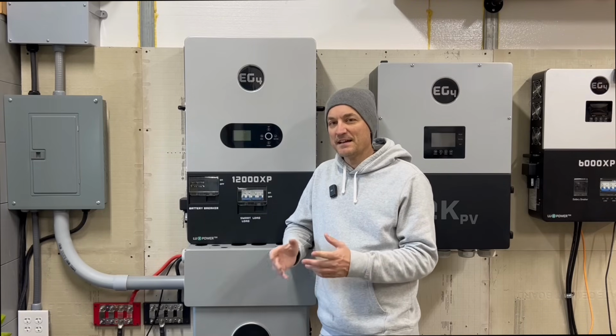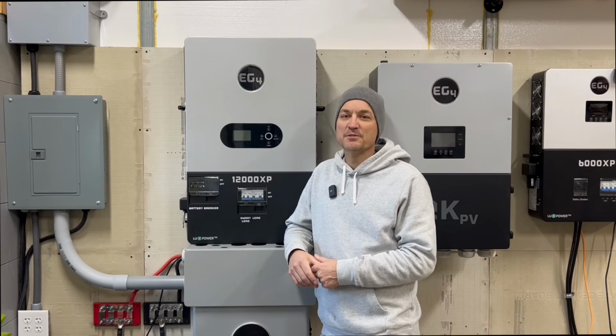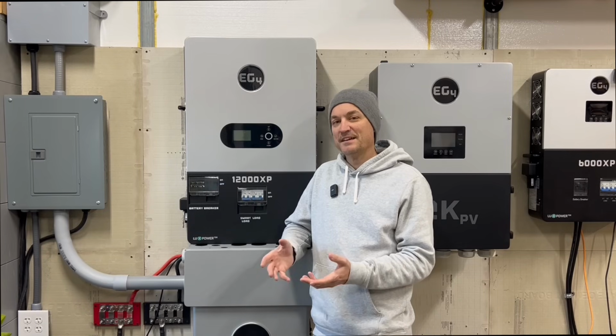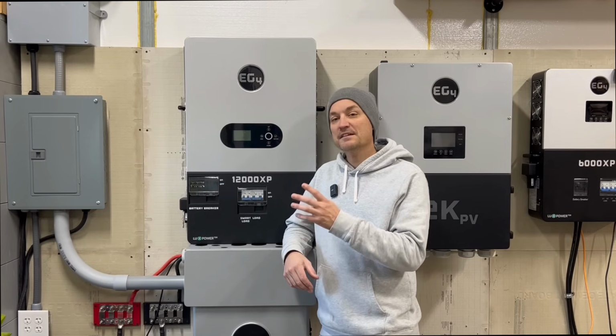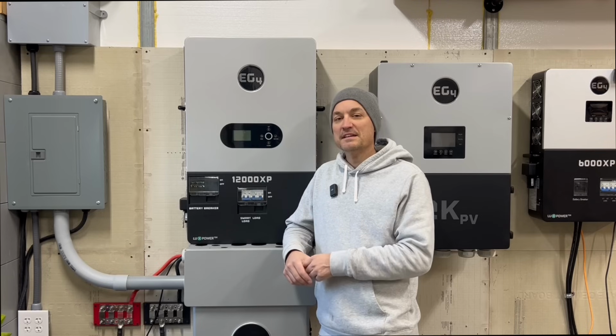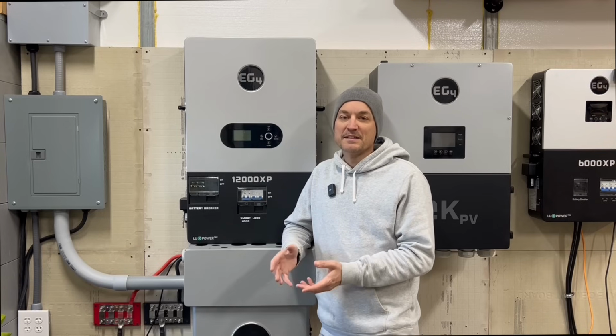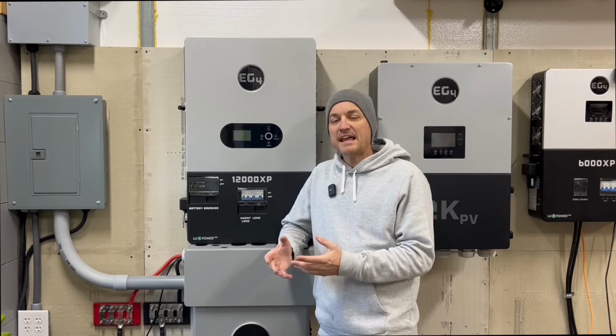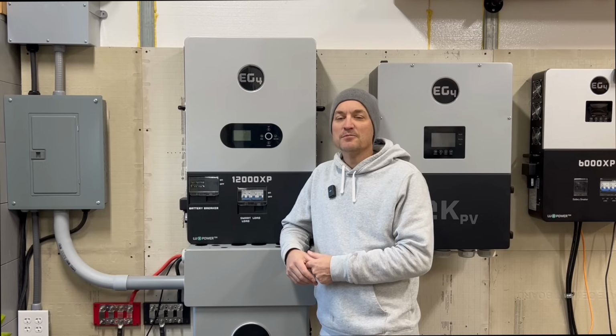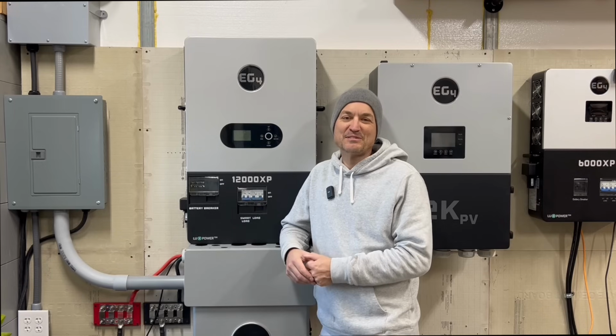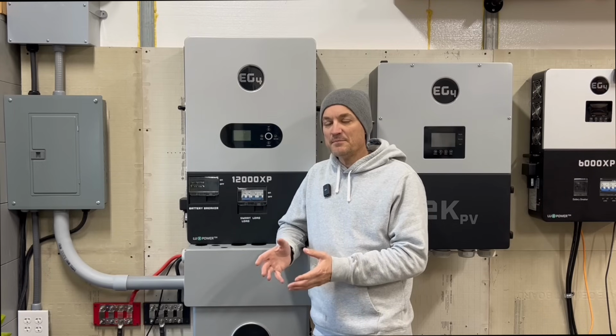You could probably easily get around 18,000 watts of solar on this unit without a combiner box. But if you want that last little bit to get you to the 24,000 watt range, which is 24 kilowatts, 12,000 watts on each input, then you're going to need a combiner box. I'm going to show you an EG4 combiner box, and I will show you what those numbers mean.